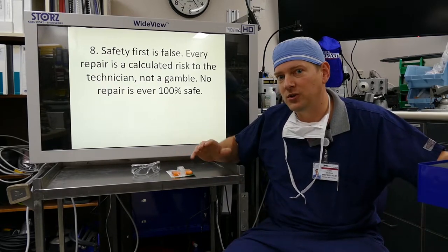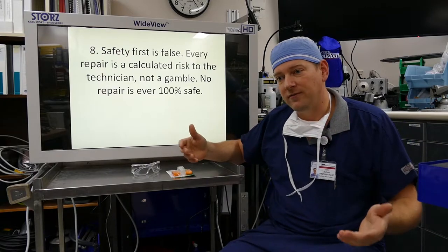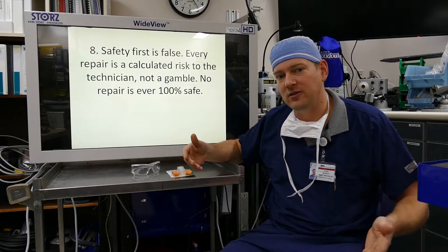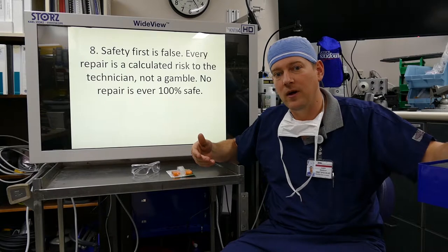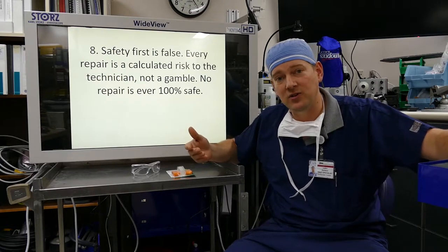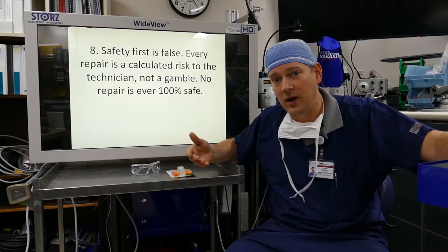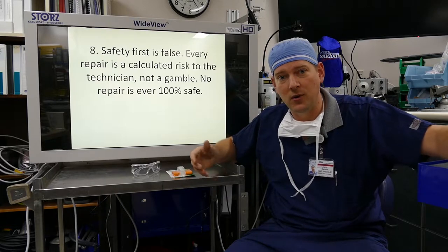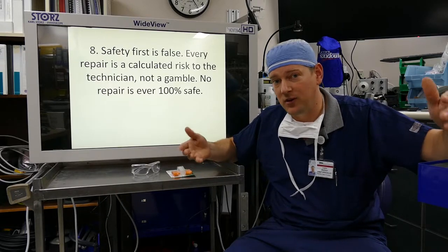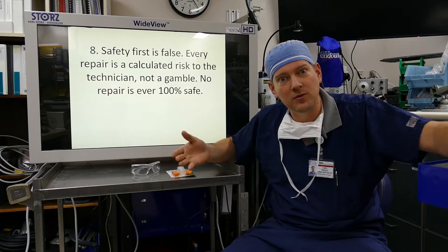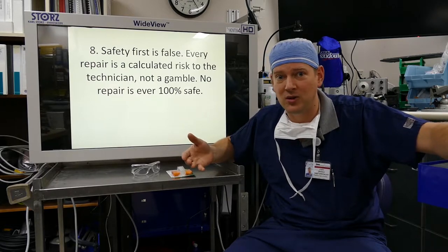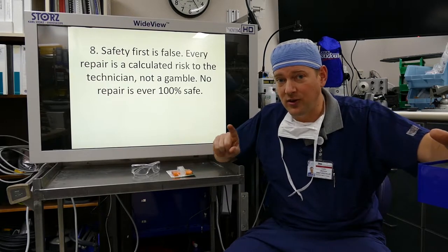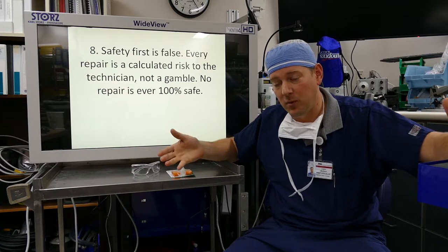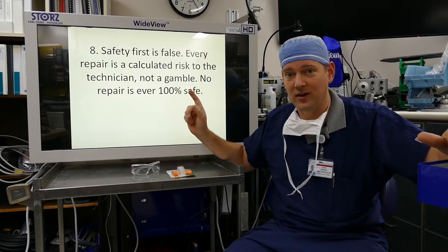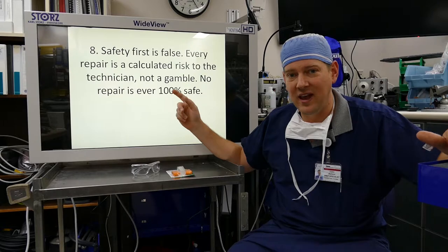You never know what you're going to get into. Sometimes you have to put your own safety at risk because you have a patient on a table. I myself have had to crawl underneath hydraulic tables and fiddle around with them, and that is a huge no-no if you don't know the nature of the malfunction, because the table could collapse on you. But guess what? There was a patient on the table and he was in way worse shape than me. So although I calculated my risk and performed the repair, it was a calculated risk. It's not a gamble. I'm not gambling here.